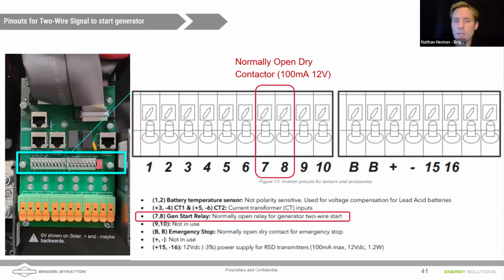Now, I mentioned that you can still use a two-wire signal to start, regardless of whether that generator is on the grid port or on the gen port. We're going to use pins 7 and 8 for the dry contactor to feed into the two-wire start signal of the generator. A dry contactor is essentially exactly what it sounds like. It does not produce any power output. It's just that pins 7 and 8 are either connected to each other or disconnected from each other inside that Solarc.